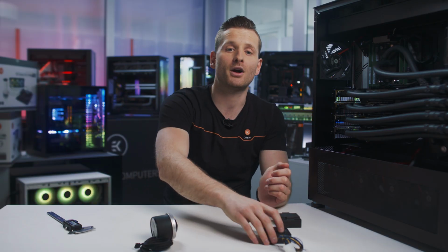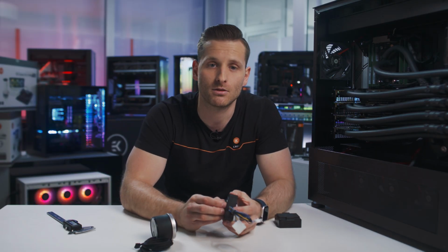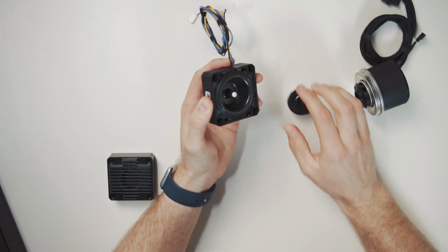The DDC pump works on the same simple spherical motor principle as the D5. The only moving part is a spherical-shaped magnet impeller rotor, which is seated on a ceramic ball right here. The rotors of both the D5 and DDC pumps are magnetically balanced and held in the designated position. Both pumps are water lubricated. In other words, they use a wet rotor design. Therefore, it's strongly recommended not to run either of these pumps dry, even for a few seconds.